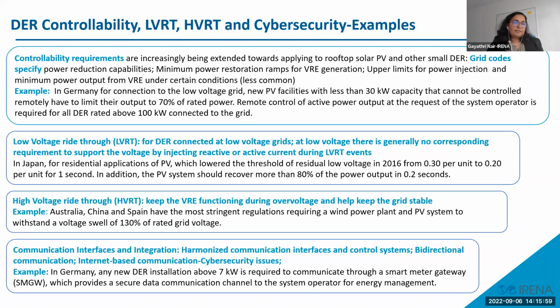Now, high voltage ride-through describes the behavior or performance of the generation asset during voltage rise, and overvoltages can be prevalent in many different situations. It can happen during faults, and during unprecedented large-scale tripping of generation or load, and all of this can impact or cause the tripping of DERs or VREs like wind turbines. To prevent this, there should be grid codes which mention that the wind turbines or the VREs should remain connected during a certain stipulated time period of overvoltage. This has been mentioned in some of the grid codes as well.